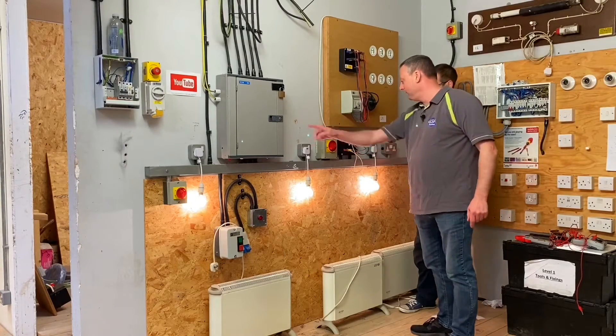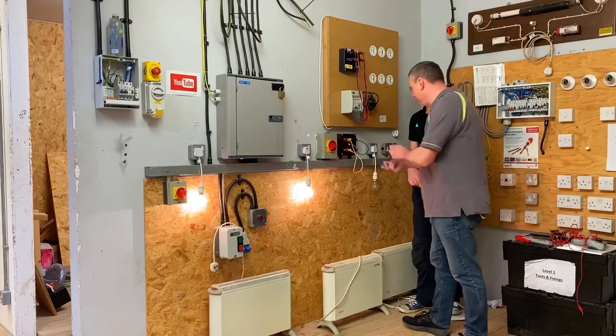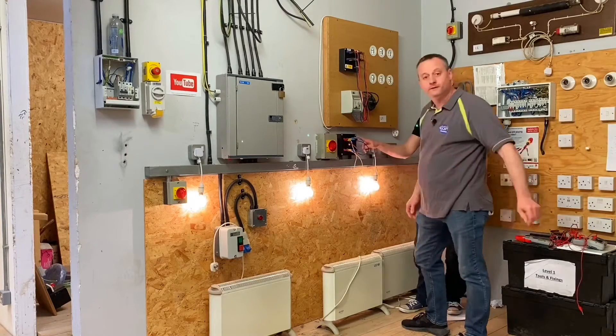So what's going to happen if we remove L3? So is that L1, L2, L3? Spot on. That'll go off then. So let's pull that one out. There you go, it goes off. I like that. So it makes sense because all of these are now wired back through this neutral conductor.